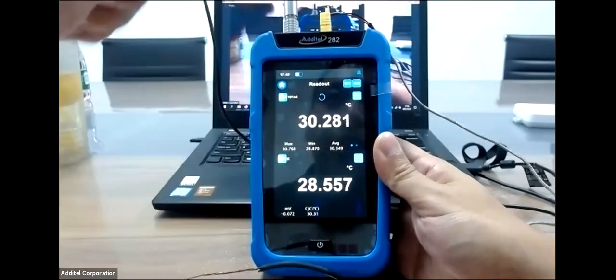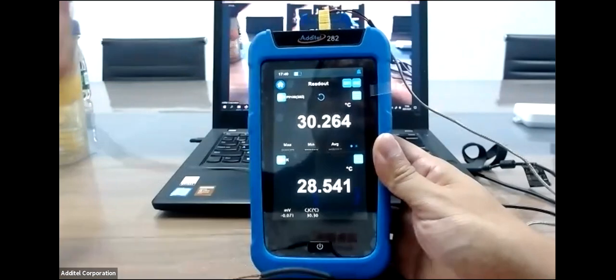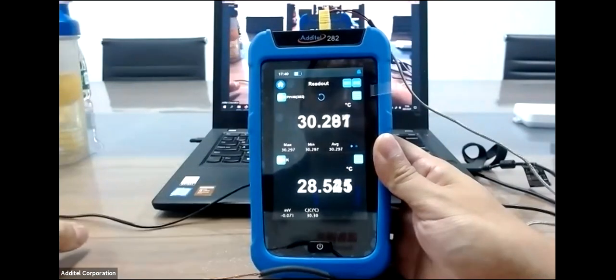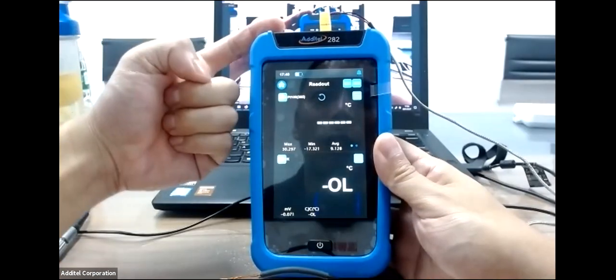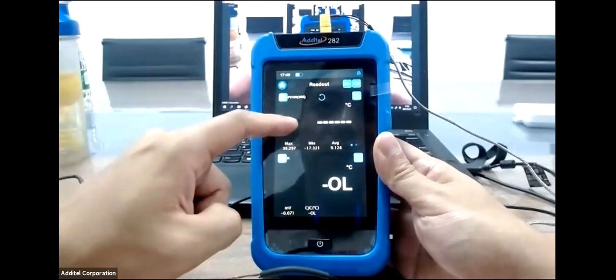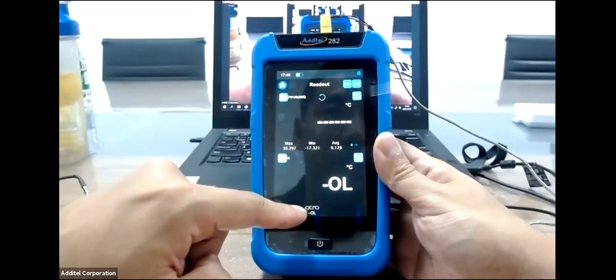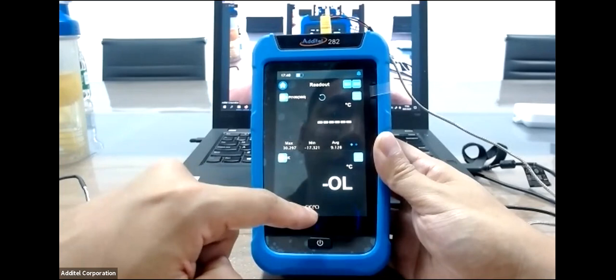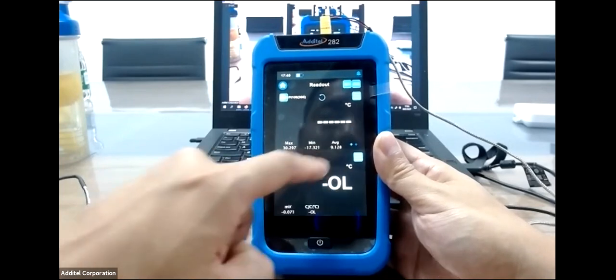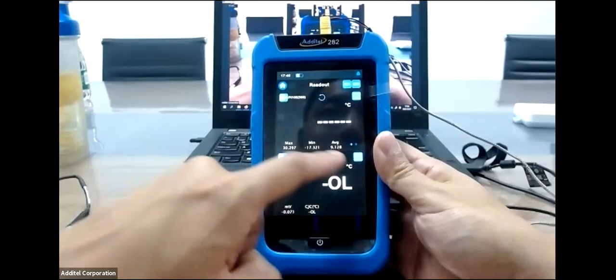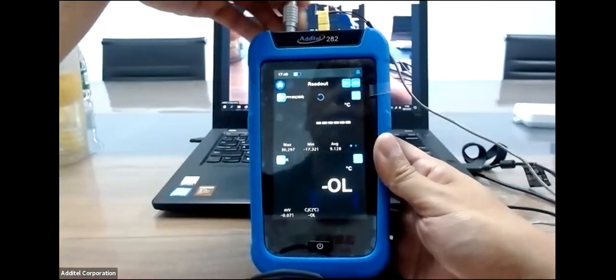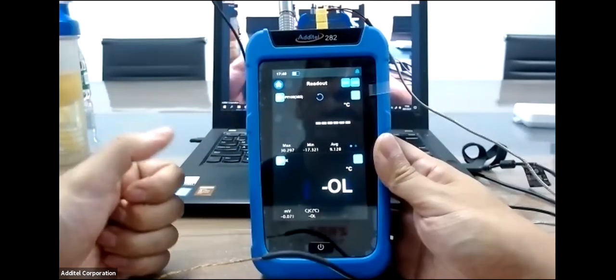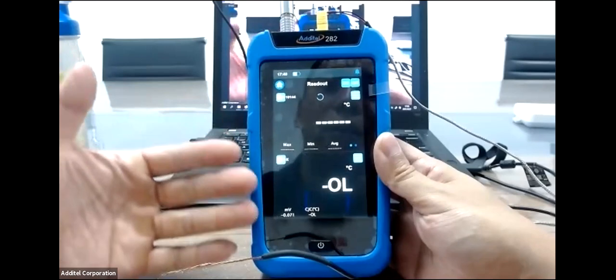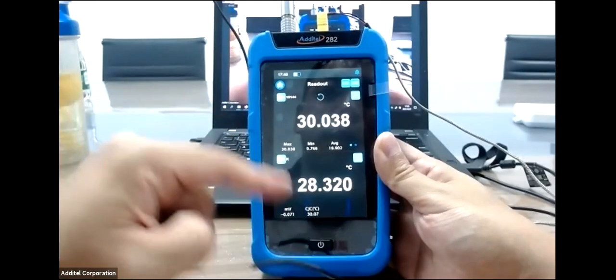If we unplug this, that means we have nothing reading on channel 1, so nothing right here, meaning nothing on the cold junction compensation. So in this way, we have no cold junction compensation, which is why your thermocouple reading is nothing. If we put it back, everything will go back, and you can see the reading right here.